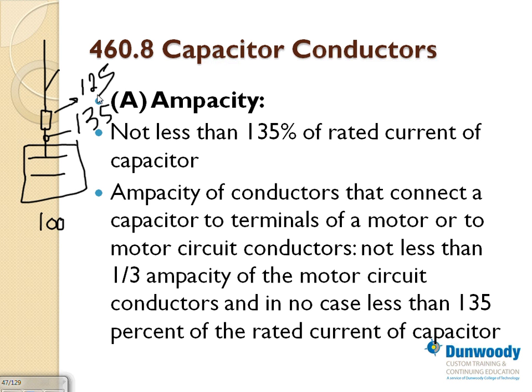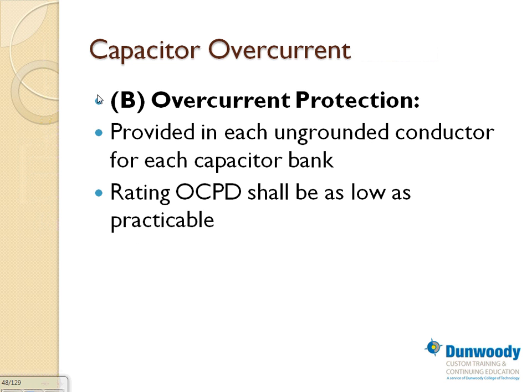Okay, so that's basically a few things, guys, about sizing the conductors for the capacitors. The overcurrent protection device, you have to put on every phase, a fuse or a circuit breaker. We size that. It says overcurrent shall be as low as practical. Now define practical for me. The code doesn't say what multiplier. In my projects, I use the same 1.35 and I go down to the next standard size. That's as practical. It works and it works good.